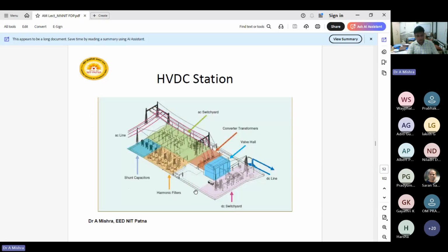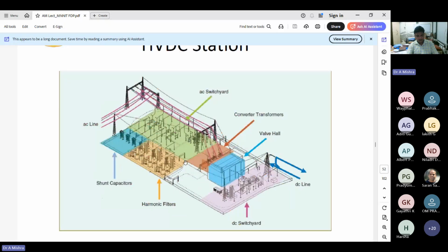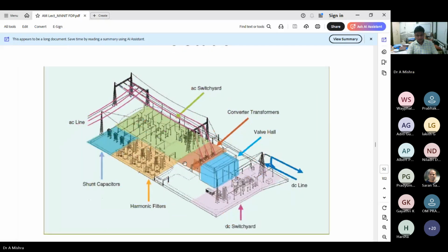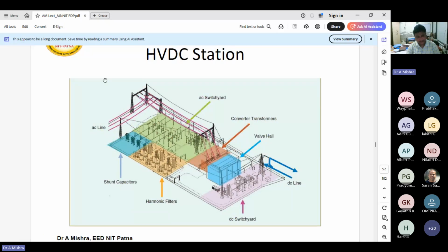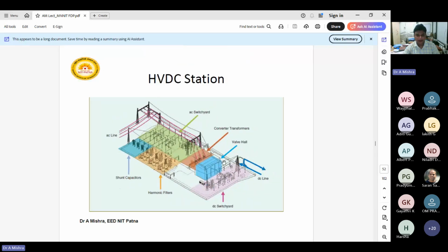This is a view of an HVDC substation. The AC station, you are already aware what kind of appearance it has. Then, if you are including the DC, first you will have the converter transformer, then the valve hall, whether it is a 12 pulse converter or a 16 or 18 pulse converter, based on the requirement. Then the DC switchyard will be there, because DC breakers and all the protection points will be used at the end, and after that the DC line goes out.